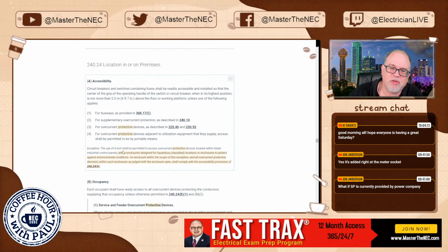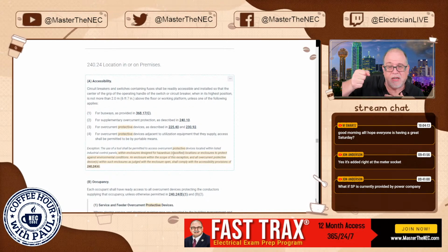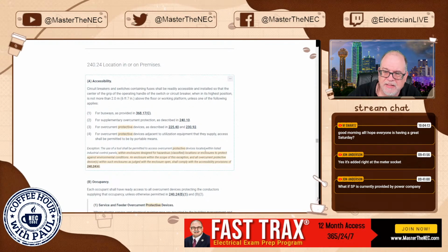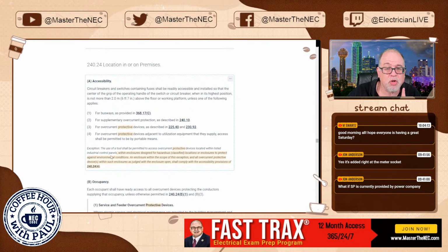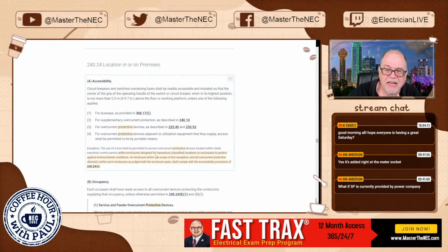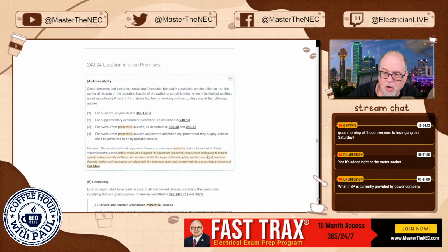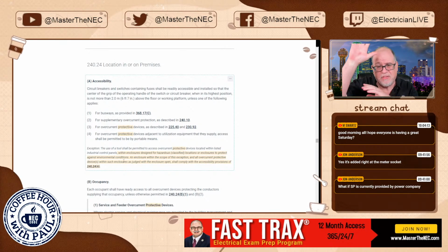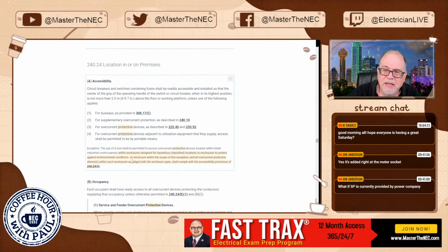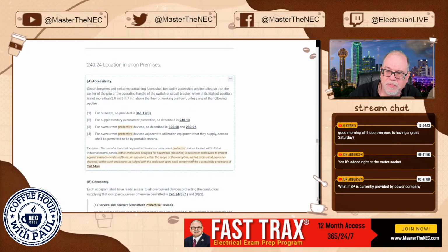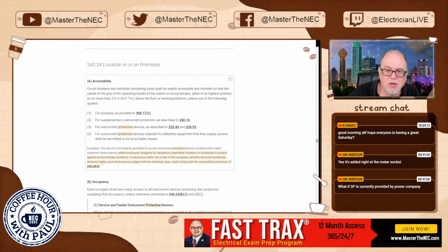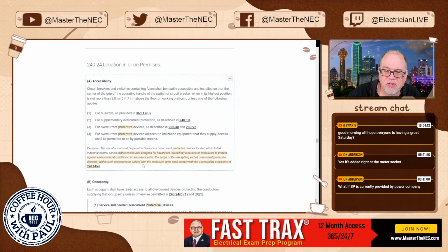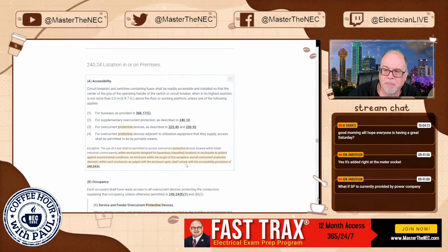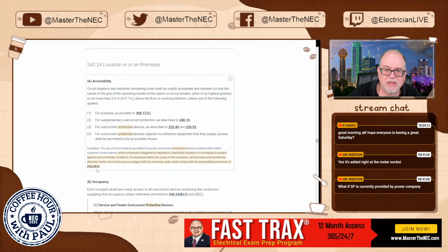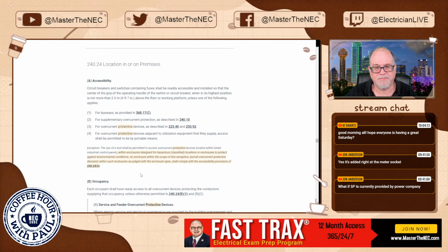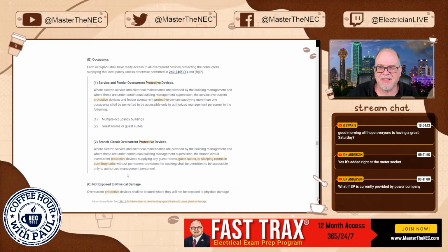It says, exception: the use of a tool shall be permitted, meaning like a pull stick or something like that, to access overcurrent protective devices located within listed industrial control panels, within enclosures designed for hazardous classified locations, or enclosures to protect against environmental conditions. Maybe it's put up high because of environmental conditions. It says an enclosure within the scope of this exception, and all overcurrent protective devices within such enclosures as judged with the enclosures open, shall comply with the accessibility provisions in 240.24(A). Okay, so again, added "protective devices" here, nothing significant again.